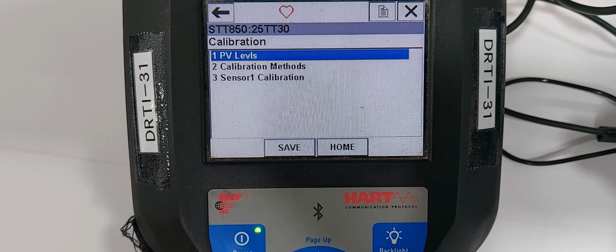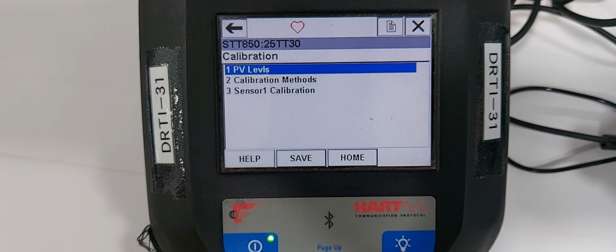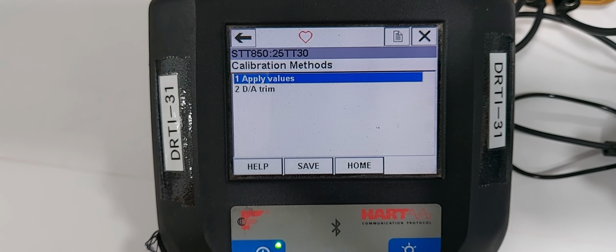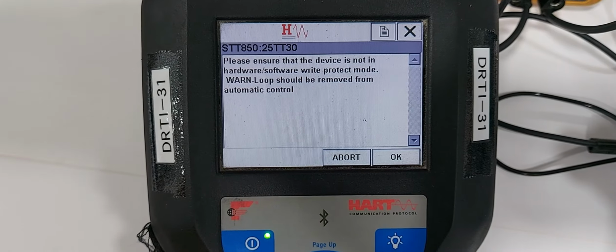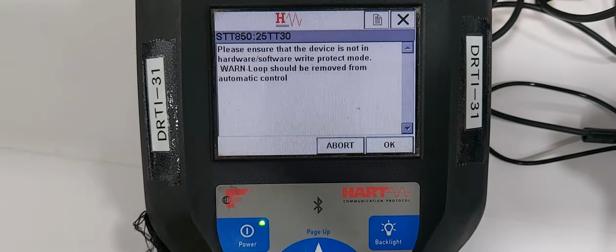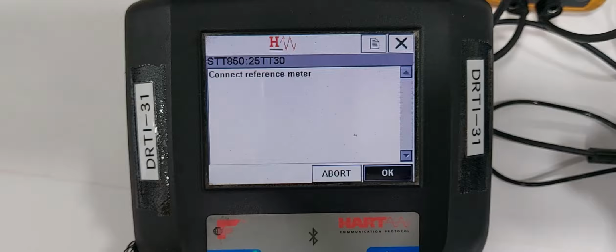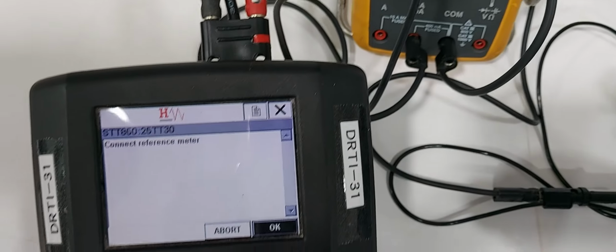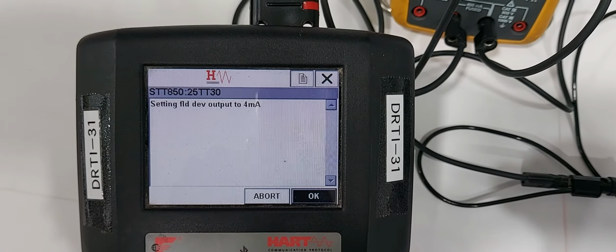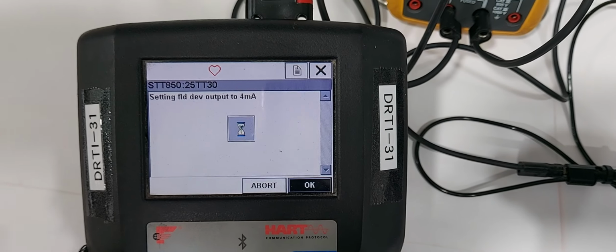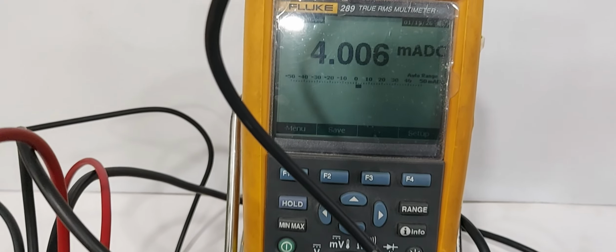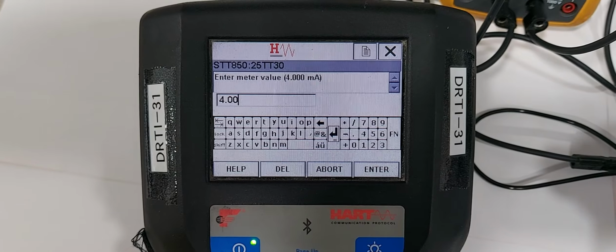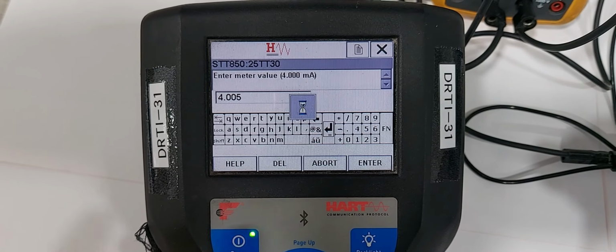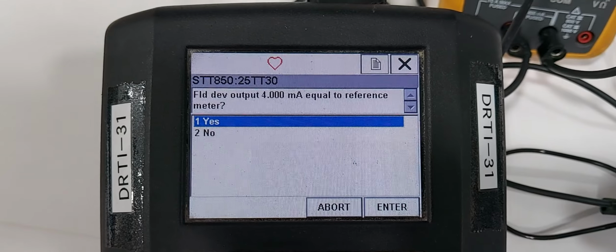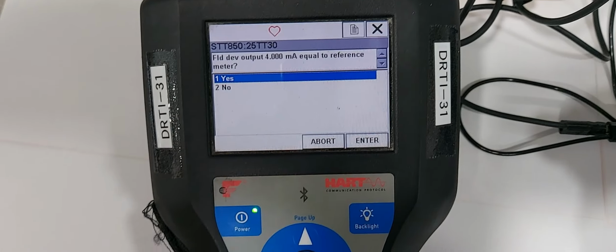First we are doing the DA trim calibration. Select the second menu and select DA trim. Remove the automatic control, then press OK. Connect the reference multimeter. Reference multimeter already connected, then press OK. Set the field device output to 4, then OK. Now output is showing 4.005 milliamps. The same reading we insert in the transmitter, 4.005, then OK. Now the reference value and the transmitter value are equal, then press yes and enter.